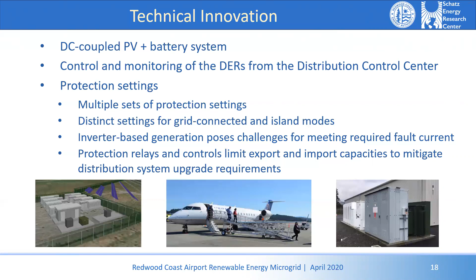Yeah, I think that's probably the main issue there. We don't have the inertia that you would have in a rotating synchronous generator. It is a challenge that engineers are very aware of these days and grappling with to find the best solution. That is happening on this project, giving PG&E more experience with that, and with monitoring and control of those sorts of things. And then finally, the protection relays. As I mentioned before, we have import and export limits that are really taken care of by the microgrid controllers, but if the microgrid controller doesn't accommodate them, they are ultimately enforced by the protection relays and the breakers that can isolate the generators if we exceed those limits.